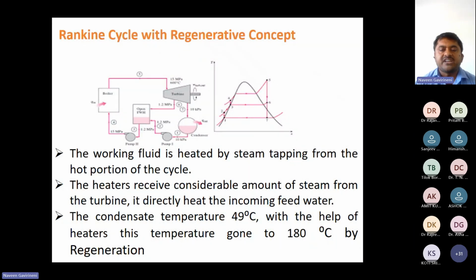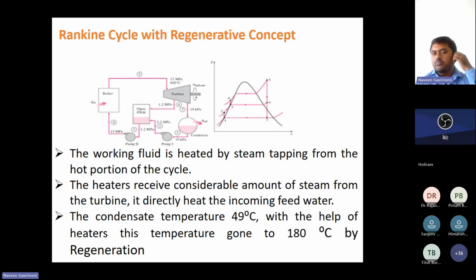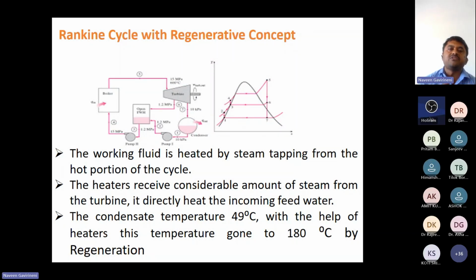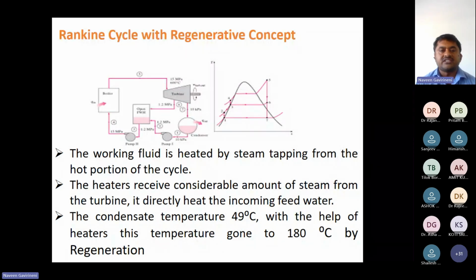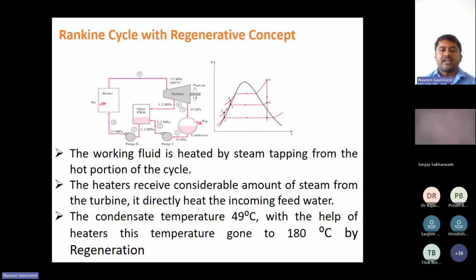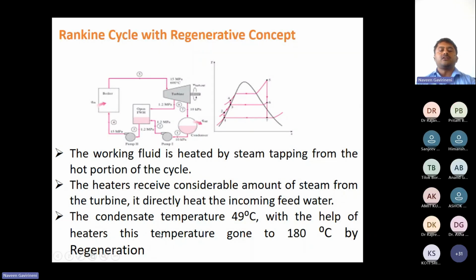So at the end of the turbine, we are getting 50 degrees temperature. But while going to the boiler, there are a number of stages of the turbine. Since we are supplying such high pressure to the turbine blades, there is a chance of steam leakage. So at any stage we have a sealing arrangement for the HP, IP, and LP turbine. For sealing we supply steam to the labyrinth gland. As per power plant terminology, in all three types of turbines you can see the labyrinth glands. So we are supplying steam to the labyrinth glands to avoid leakage.